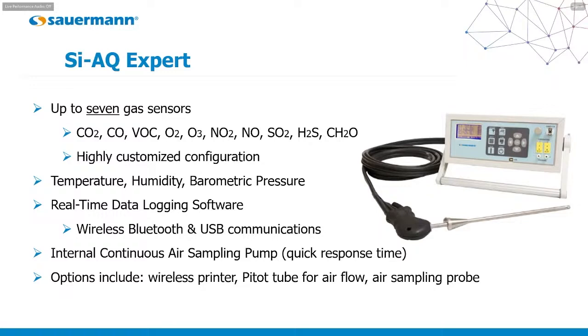is, once again, it can have up to 7 gas sensors. So you can see all the gas sensor options listed there, which are all the same gas options that we talked about for the handheld instruments, including the VOC, whether it be a low or a high concentration VOC sensor. And then in addition to what we talked about before, you notice after oxygen, we list O3, which is ozone. So it also has the ability to add an ozone sensor. So once again, CO2, carbon dioxide, carbon monoxide, VOCs, oxygen, ozone, NO2, NO, SO2, H2S, and formaldehyde are all different gas sensors you can have in this model. And as I mentioned with the handhelds, you have the ability to mix and match and choose those gas sensors however you wish. So once again, you can customize it to meet whatever the requirements are for how it's intended to be used in the field and for whatever type of applications you plan to use the instrument in the field.